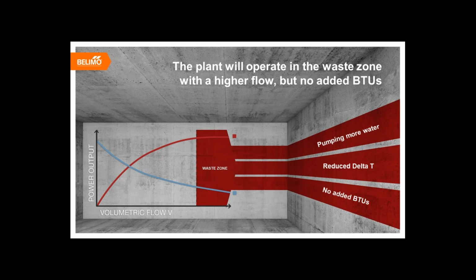A plant will operate in the waste zone with a higher flow but no additional BTUs. As you can see, we pump more water, our delta T is reduced, and we do not add additional BTUs for the extra pumping or the additional flow. So basically, the waste zone represents all the additional water that a coil cannot use. This is the lost efficiency, lost money, or wasted resources.